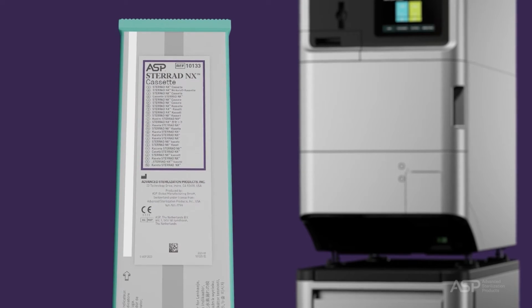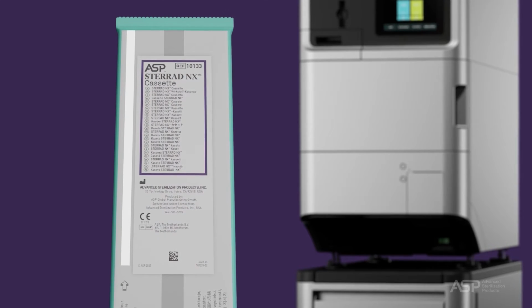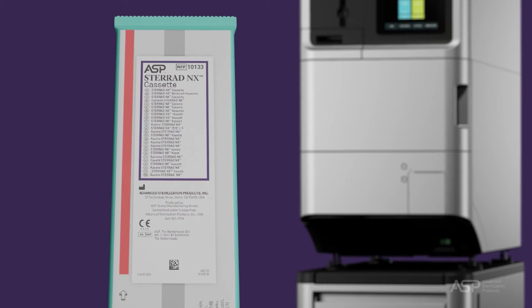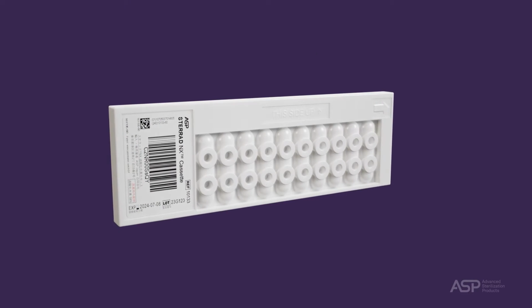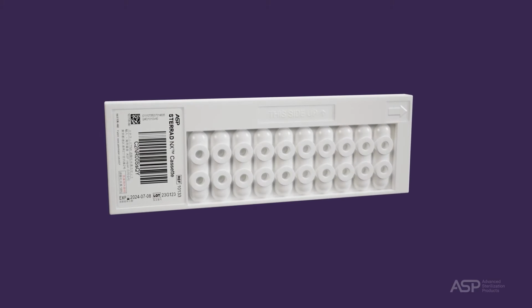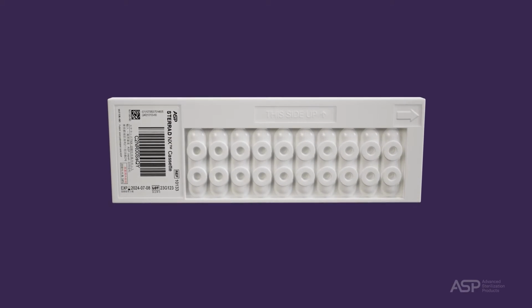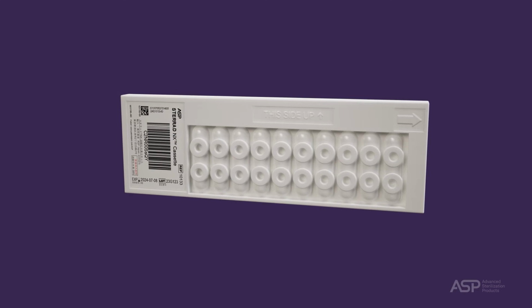Observe the leak indicator strip on the wrapped cassette. If it indicates a leak, the strip changes from white to red. If the strip is red or you see droplets of moisture, do not open the package. It's possible that hydrogen peroxide has leaked inside the package.